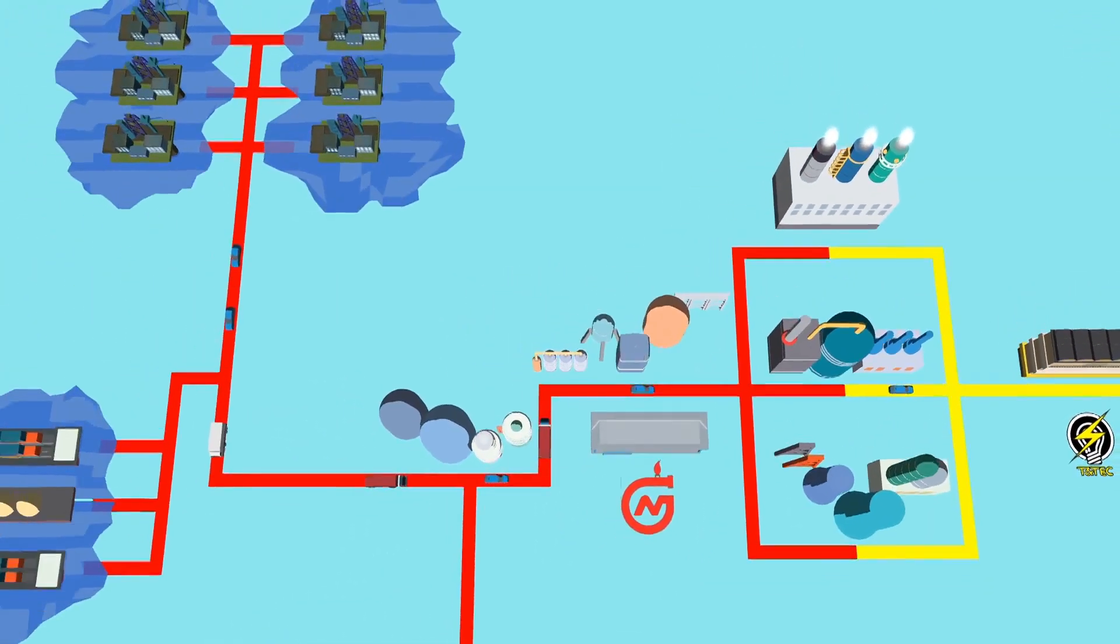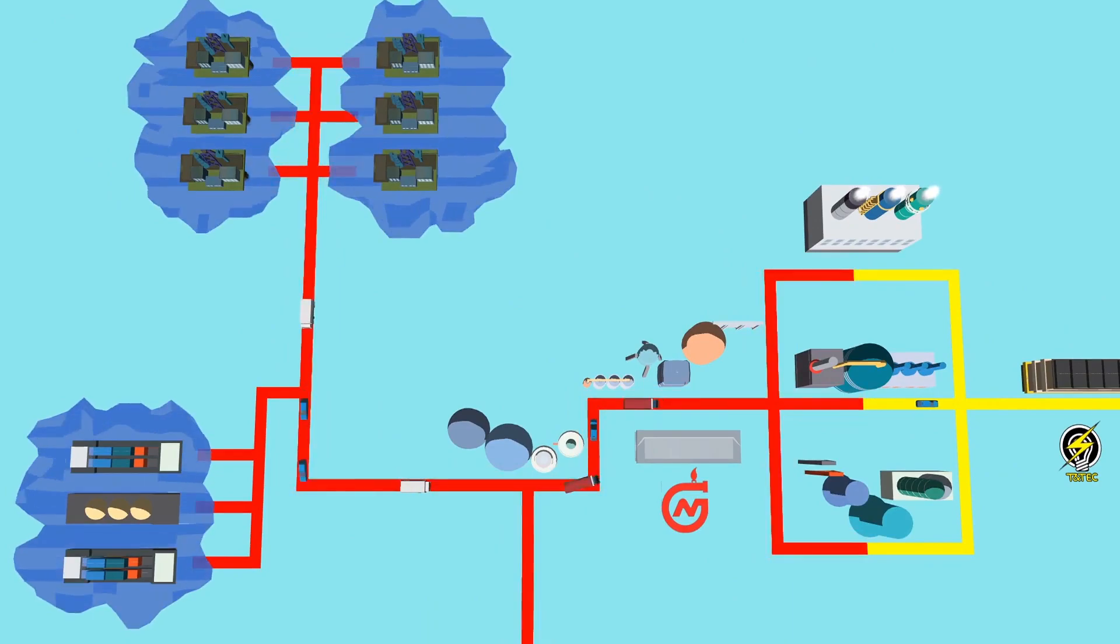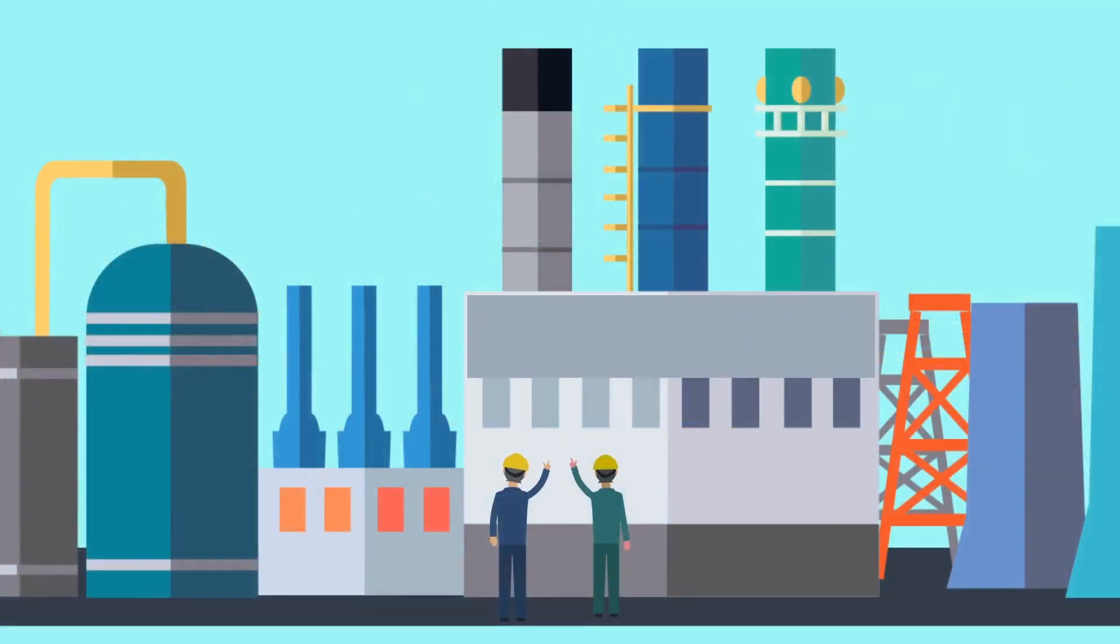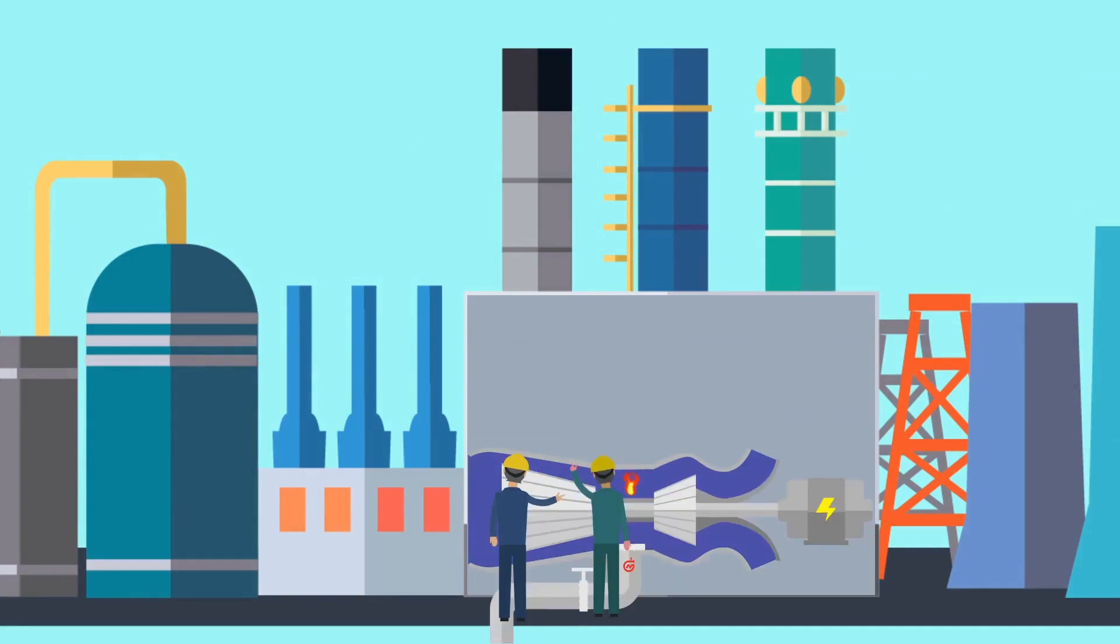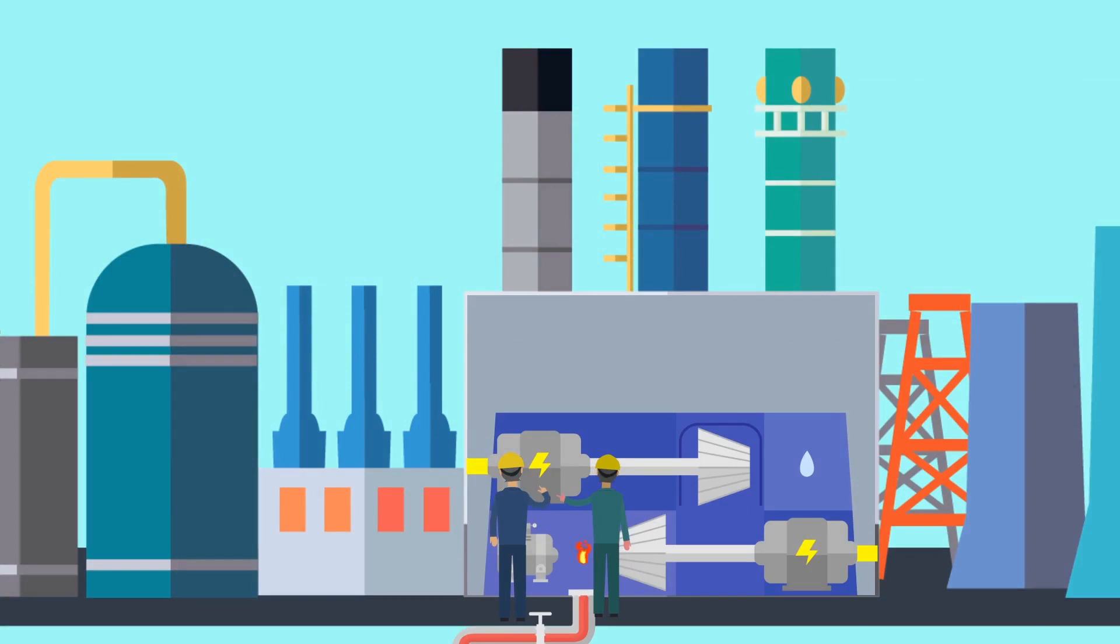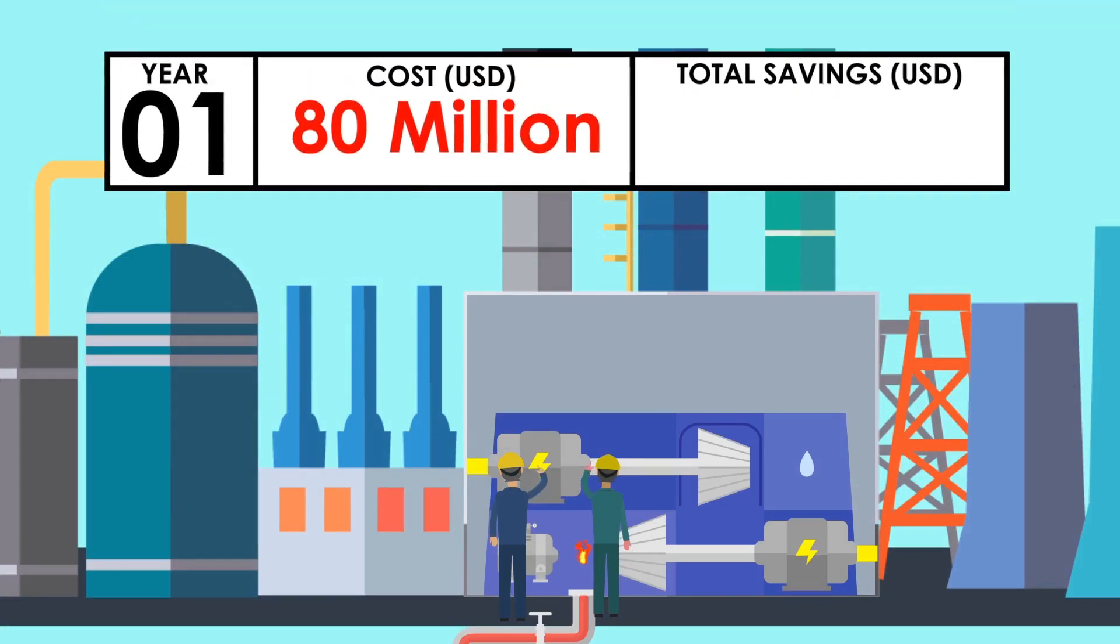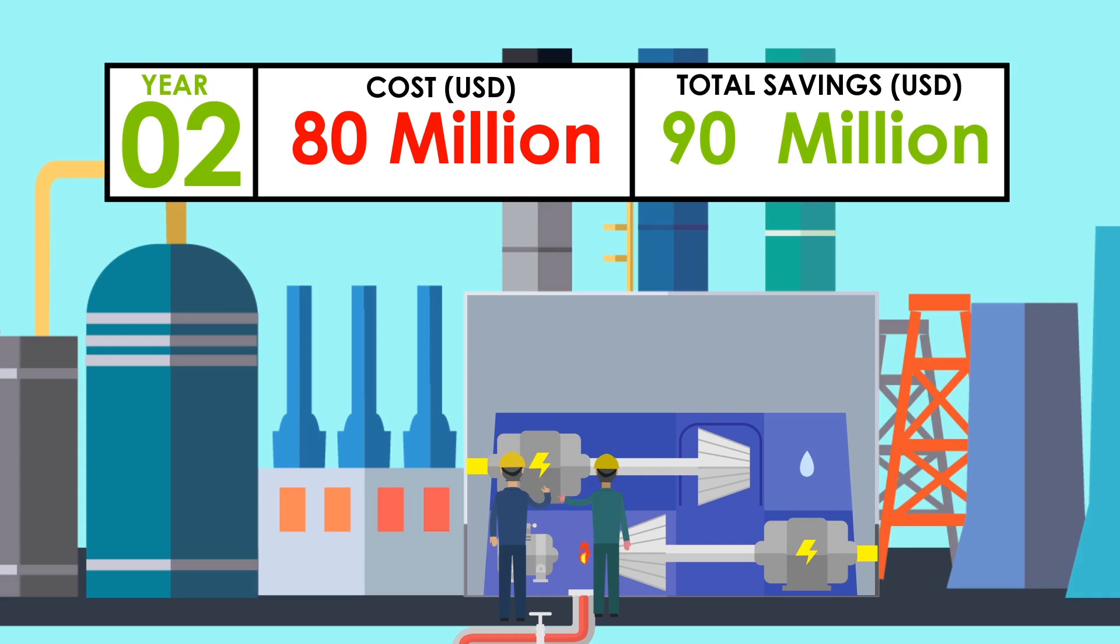Where we are now facing a natural gas shortage, are these losses at the power stations acceptable? Analysis by PowerGen engineers has shown that recommended upgrades to some of their turbines, from open cycle to combined cycle, could cost about US$80 million, but could save us US$45 million per year in natural gas. This represents a payback period of less than two years.